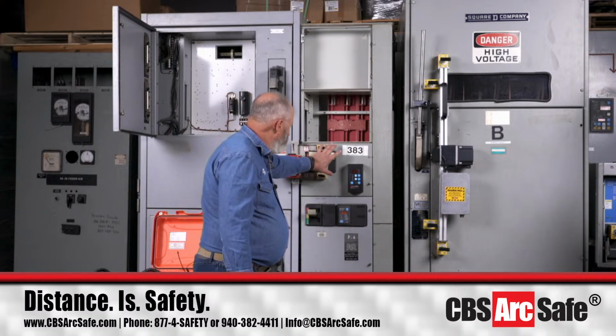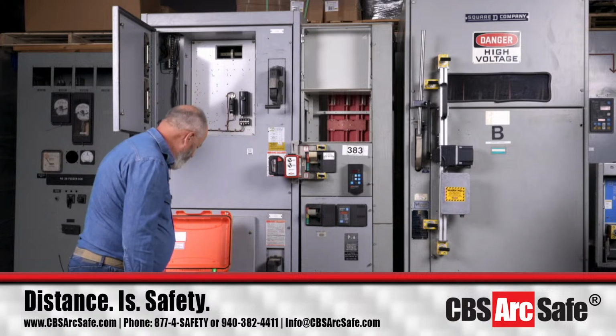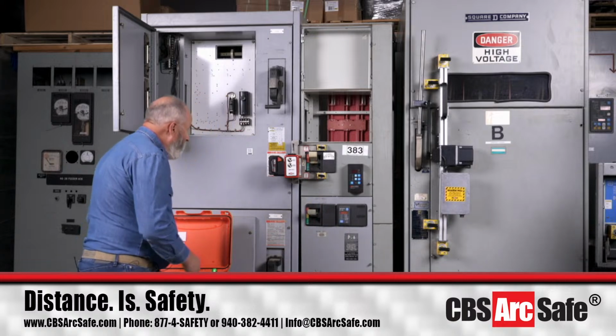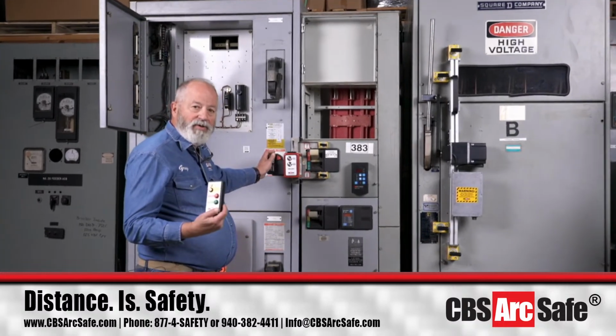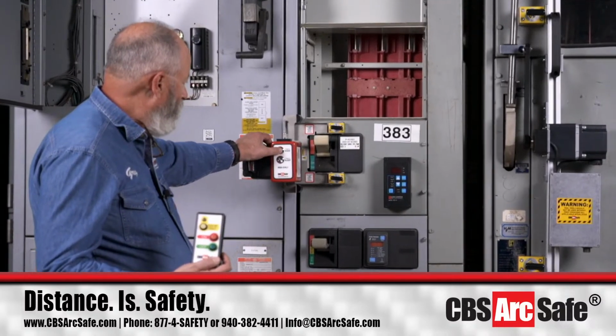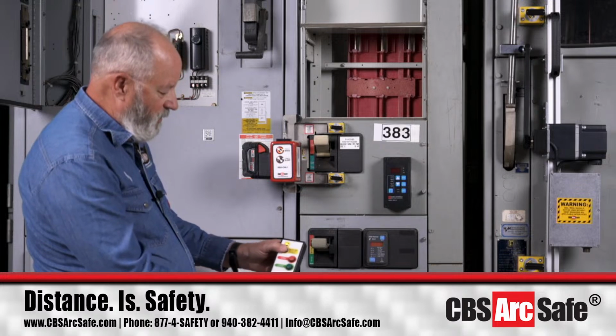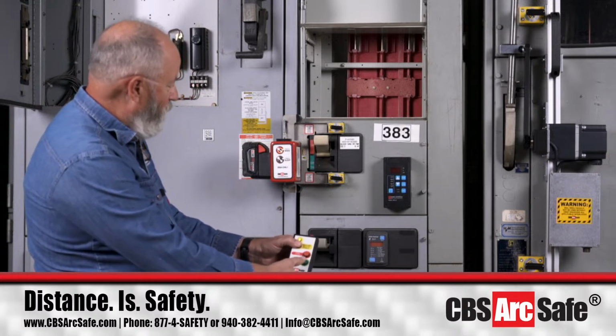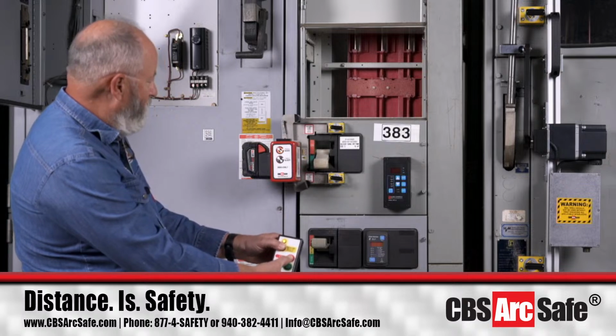The RSA 78A would handle what we call the size 5 or the main bucket, okay? Because it's got a much larger handle, it stands out on the face, and you've got an 800 to 1200 amp breaker back behind it. For this one, we use an M18. This is wireless, so we can operate this well outside of the arc flash hazard boundary. We'll push our wake button here. Then we have to hold down our on button here. And we'll hold down our off button to turn it off, and our on button to turn it on.